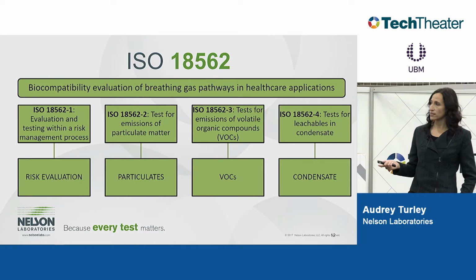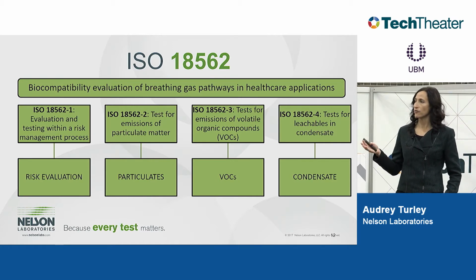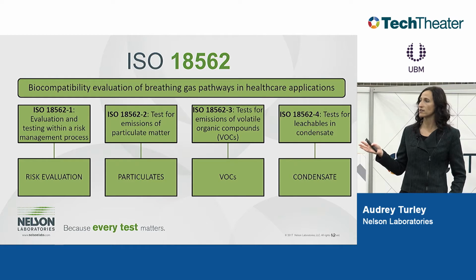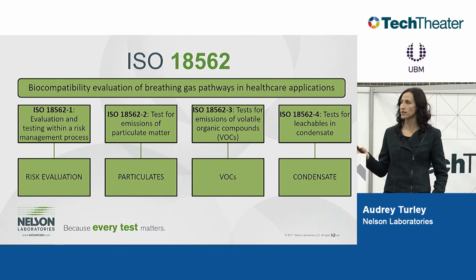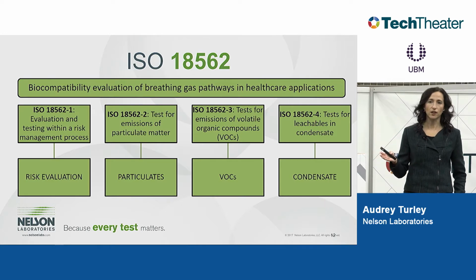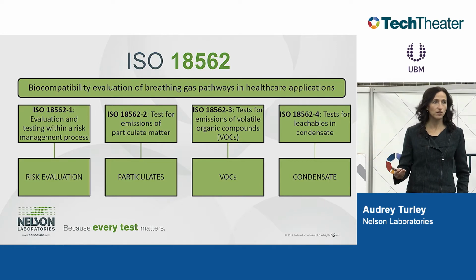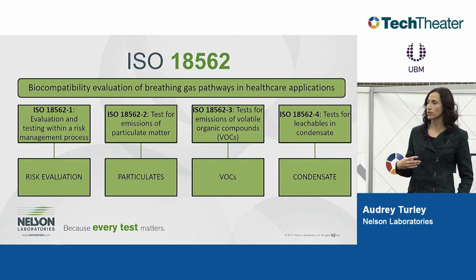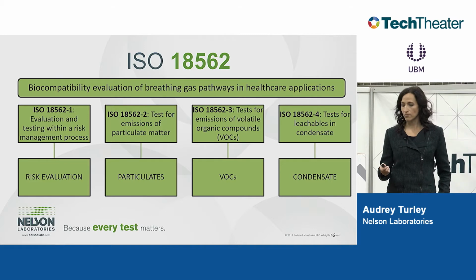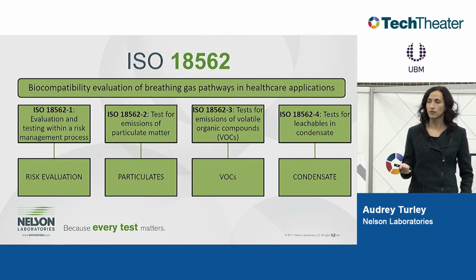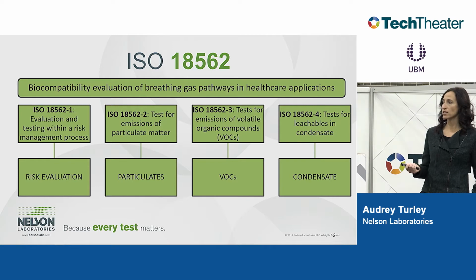So for ISO 18562, this is just a summary of the standards that are incorporated under this. There are 4 parts. The first one is still the initial risk assessment. So we do our risk evaluation here and assess the type of device, how it's used with the patient, our patient population. We're going to talk about our materials. This is all done in our initial step 1. Part 2, we're going to address particulates. That's a special risk to patients where it's going straight into your lungs on these gas pathway devices. Part 3 covers testing for VOCs, volatile organic compounds. And Part 4 covers tests for leachables in the condensate if you have a humidified gas pathway.